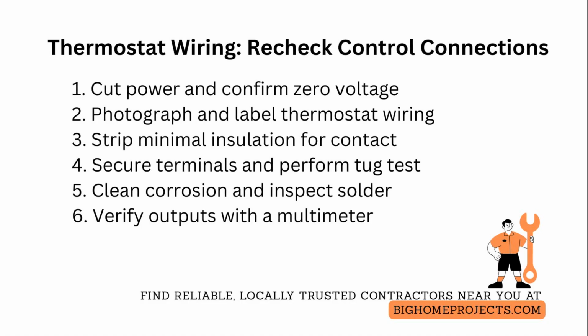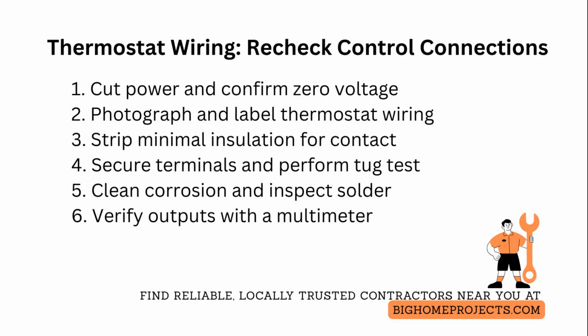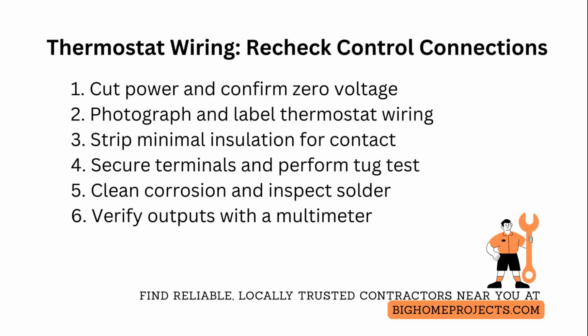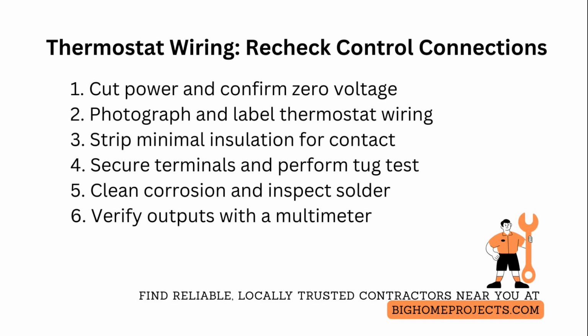Label each conductor with tape and a fine tip marker to prevent miswiring during reinstallation. Strip only as much insulation as needed for a solid wrap or secure terminal capture. Too much exposed conductor increases short risk. Too little prevents reliable contact.